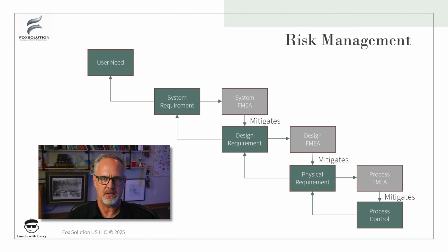And that puts us in a position where, when we get the post-market data back in, we can associate it with a line in the FMEA and have a very clear understanding of what our contract with the FDA is. It's not a contract, but you understand what I'm saying. If I say it's 1 in 1,000, and I justify deployment of the device based on 1 in 1,000, and it comes in at 1 in 100, I have a problem.